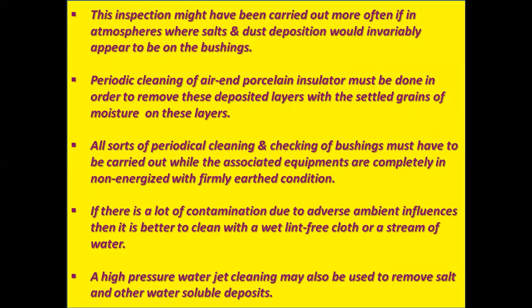Periodic cleaning of the air-end porcelain insulator must be done in order to remove these deposited layers with the settled grains of moisture on these layers. All sorts of periodical cleaning and checking of bushings must be carried out while the associated equipment is completely non-energized with a firmly earthed condition. That is, it must be in offline condition.